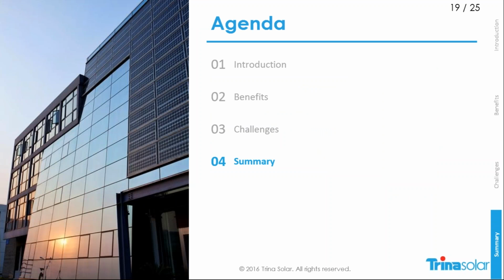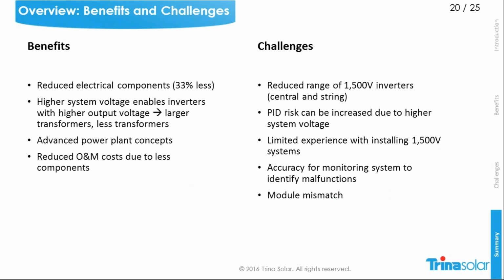At last, I want to give you a summary of the points we already discussed. First, we have some benefits. Those benefits are for sure the reduction of the electrical components due to the longer strings, approximately 33%. Then the higher system voltage also enables new power plant concepts. That means larger transformers, a smaller number of transformers, higher output voltages of the inverters and so on. And for sure reduced operation and maintenance, because you don't have to maintain so many inverters.